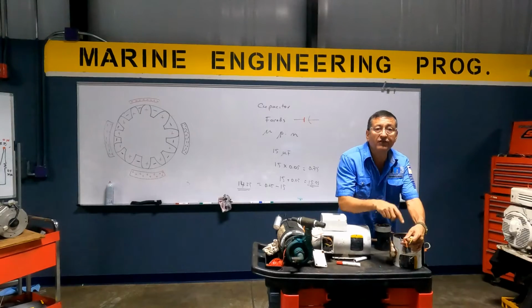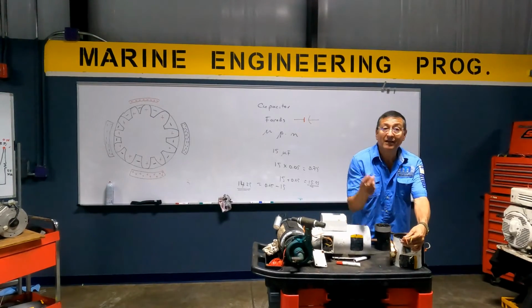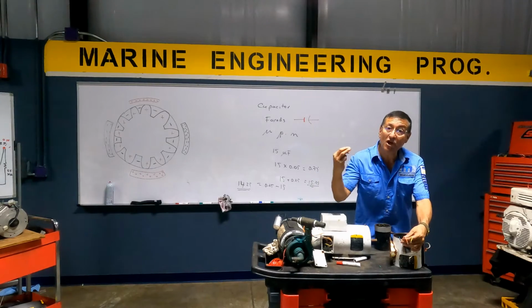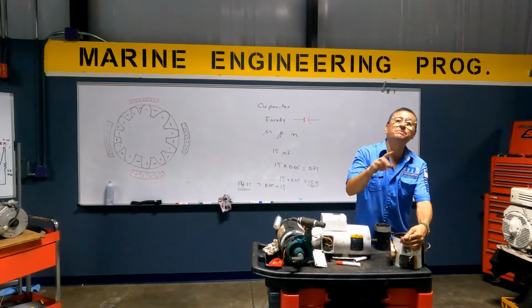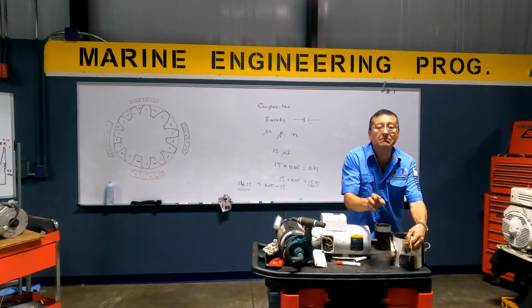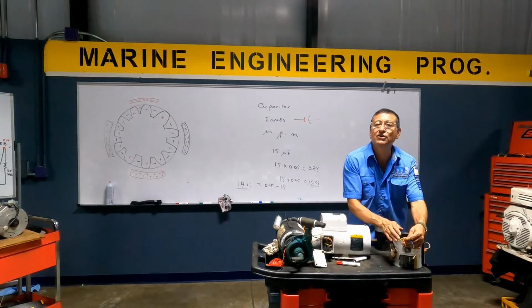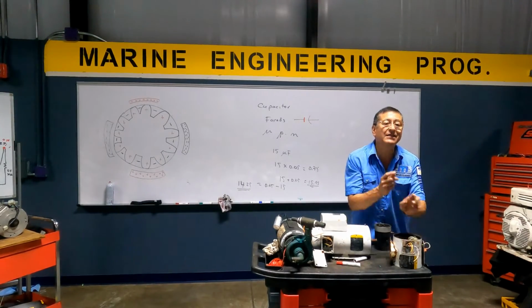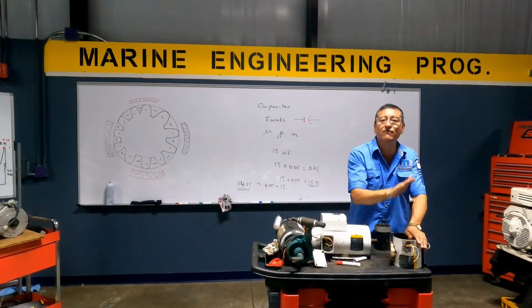Okay, pay attention. The advantage of this motor is that when you switch 2 of the 3 phases coming in, this with this, the motor spins in the opposite direction. Which one can I switch? Any. You can switch this with this or this with this, any of those. You switch 2 phases and the motor spins in the opposite direction. This is a great advantage of those motors.